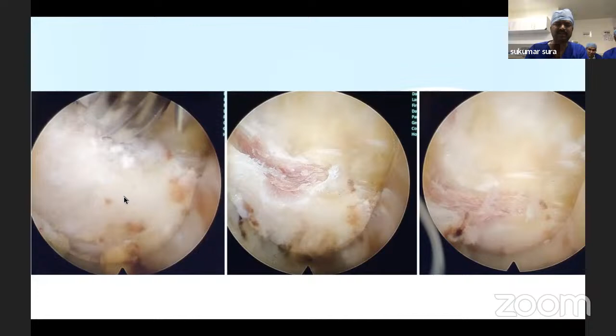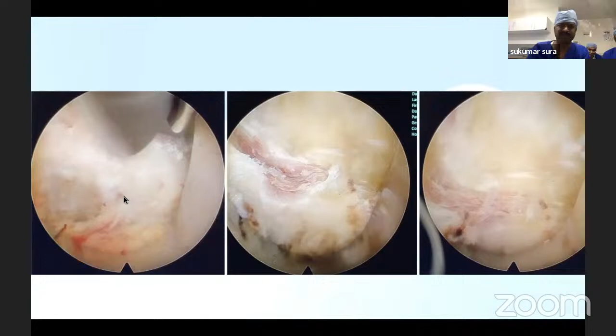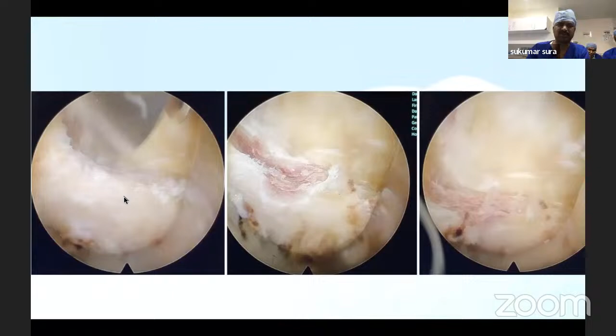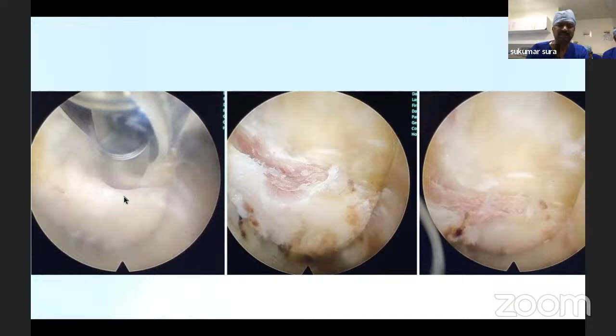When you use the belly of the burr, we can do it much faster. Our RPM would be around 3,000 to 6,000 here, so no need for more RPM. There is no wobbling here, because when your torque is good and you have a good motor, it doesn't wobble at all. You can see I use the tip of the burr. Now I use the belly of the burr. When you want things to be done faster, you can use the belly of the burr so that it cuts faster, and it doesn't plunge because you are only using the side of the burr. So your work is always outwards. So there is no plunging here. This is a very important tool in endoscopic spine surgery.